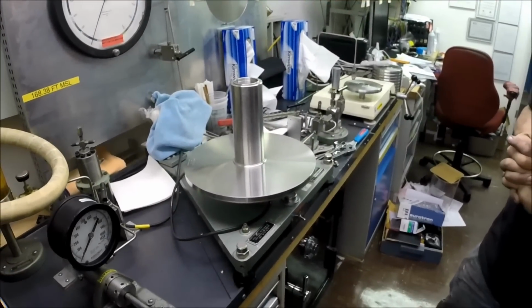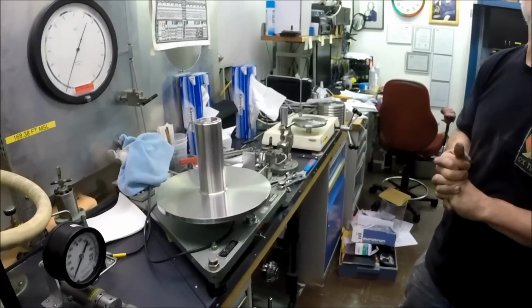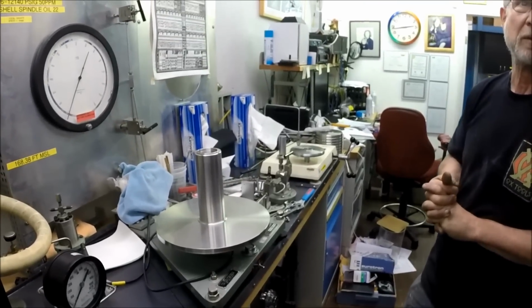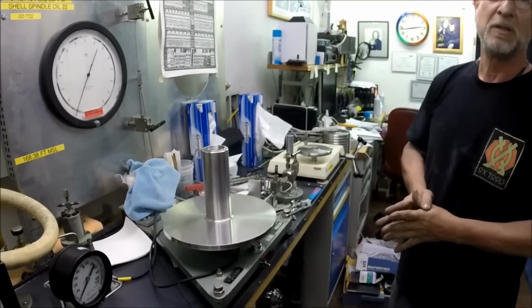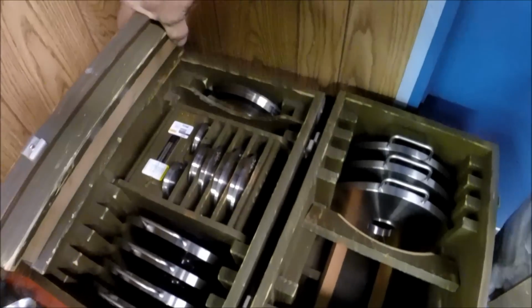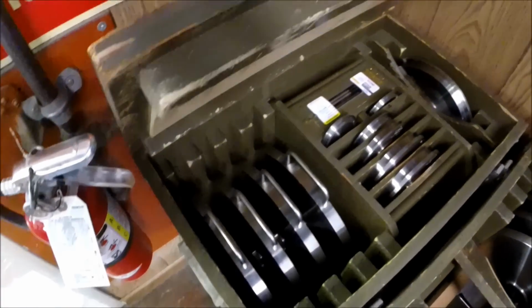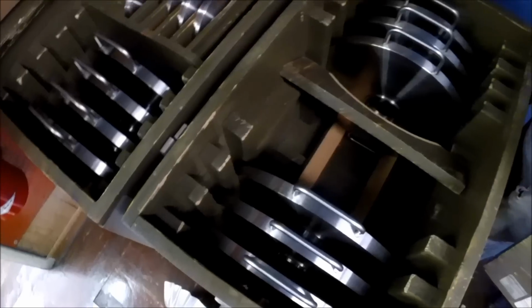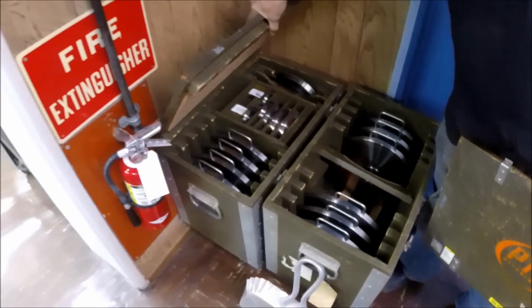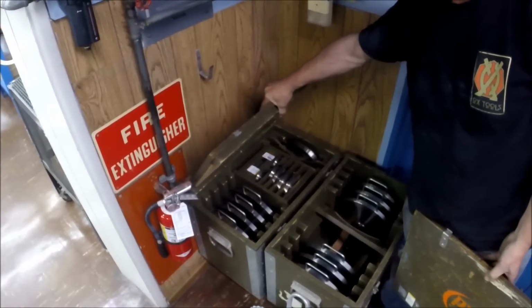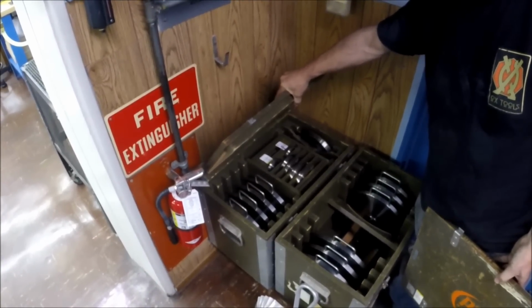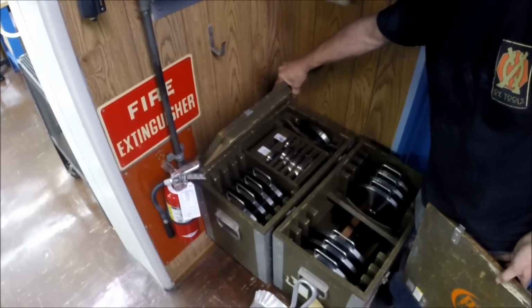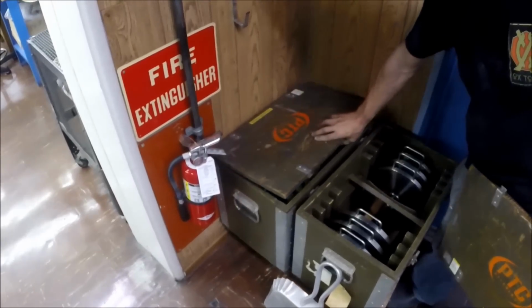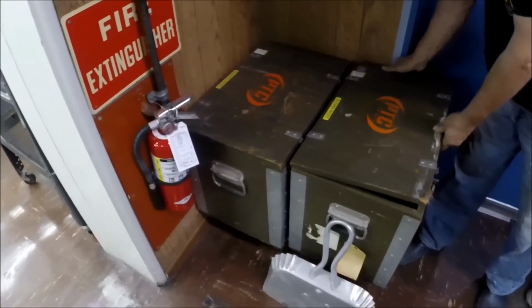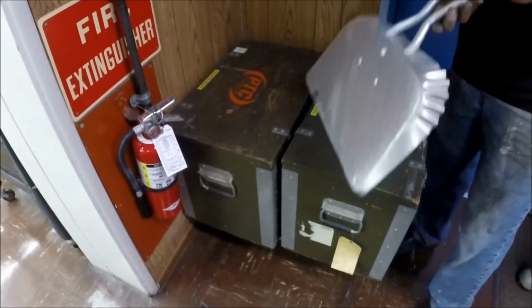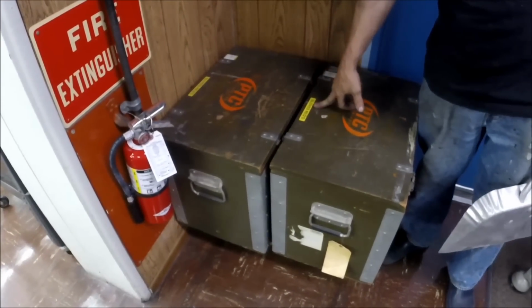Which is really nice. The standards at NIST in Colorado are not significantly better than this. This is really the technology that generates pressure. So there's several hundred pounds of additional weights to get up to the 10,000 psi. Each platter here is serial numbered, weighed individually to, if my memory serves correctly, about 100 parts per million. And so when you stack them, that uncertainty tends to cancel out. Some are a few millionths heavier, a little bit lighter, and these are strictly a gloves required item.